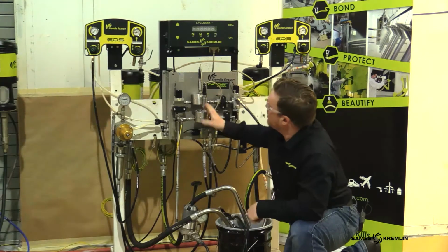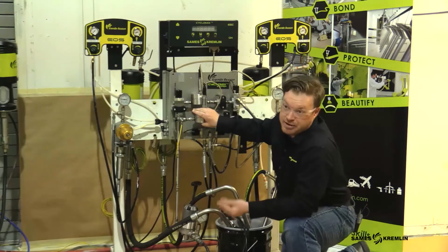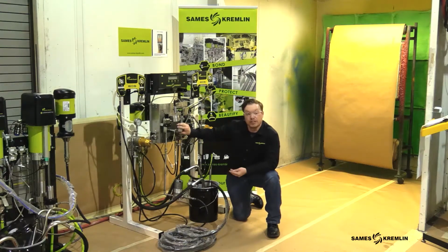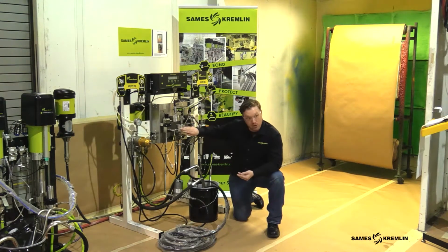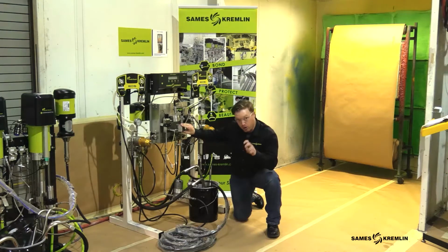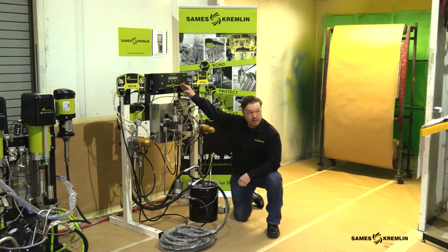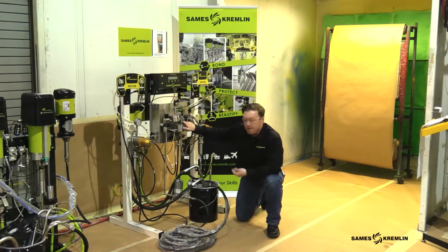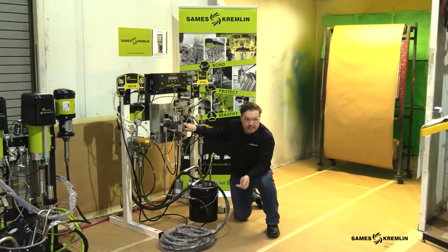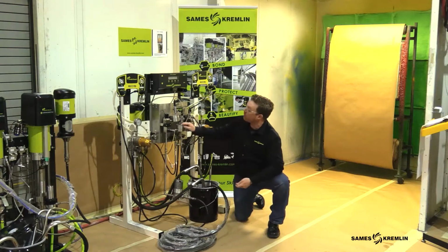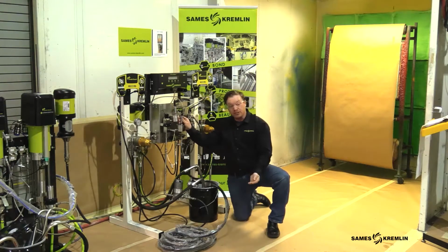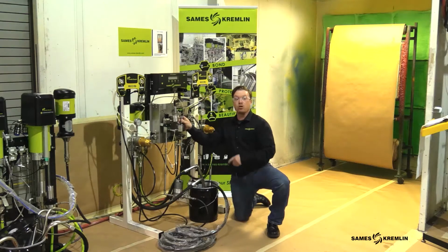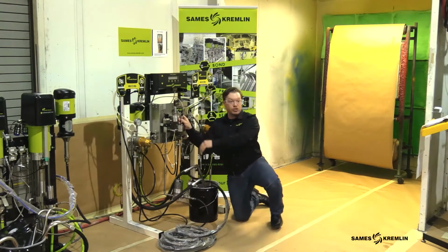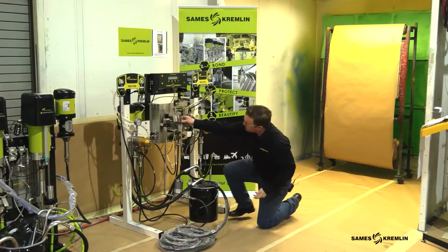There's something with the flow meter called the K factor, and the K factor for this machine is 0.24 cc's. That's the amount of material that passes through the flow meter per tooth, per pulse, that is sent back to the controller. So for every 0.24 cc's of material, we're getting a pulse. The calibration is what translates that into actual cc's for consumption and ratio monitoring.